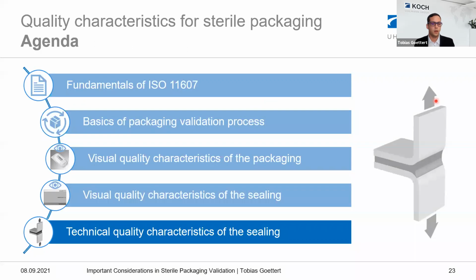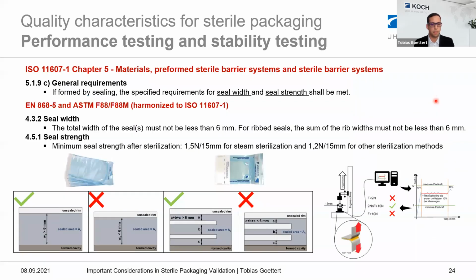So probably we are now at the last topic, the technical quality characteristics for the sealing. Therefore we have to go again deeper into ISO 11607, and in chapter 5 it gives some general requirements. It says, if formed by sealing, the specified requirements for seal width and seal strength shall be met. Shall be met means you have to specify the requirements for the sealing width and the sealing strength. So let's start with the sealing width. For the sealing width, usually you're free to define it for yourself. But it's always easier, I would say, to reference some official standards.